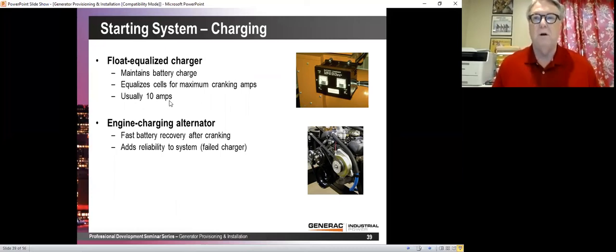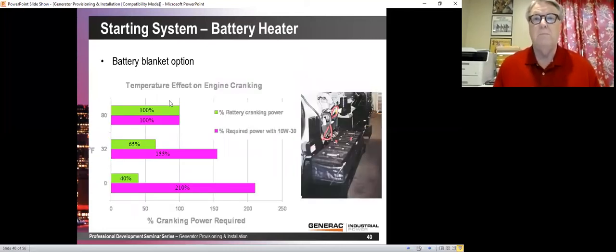so it only puts enough charge into the battery to keep it at its optimum charge. Smaller generators can come with 2 amp trickle chargers. Not as good, but if you're buying a residential generator or a small commercial generator, or maybe even a small industrial, that is standard. The 10 amp costs a little more, but we typically tend to recommend it and to put it in.